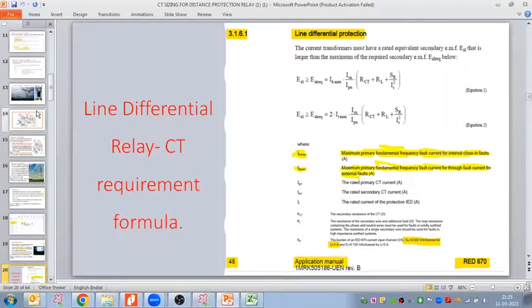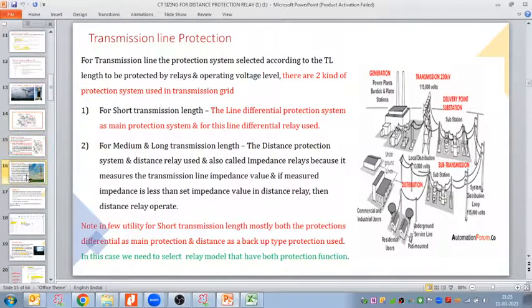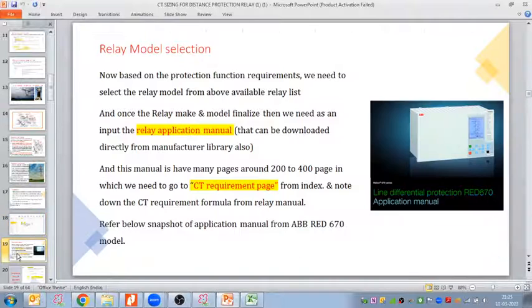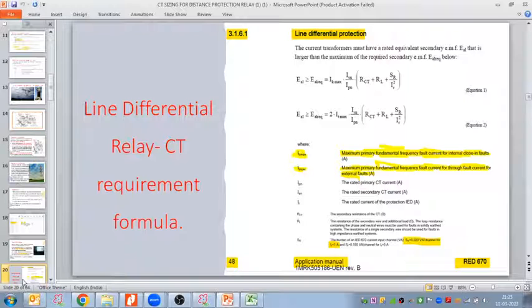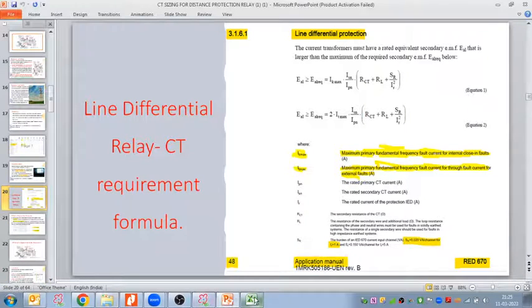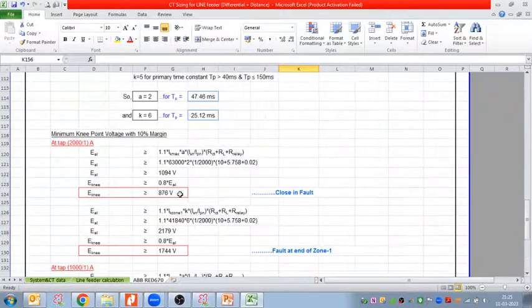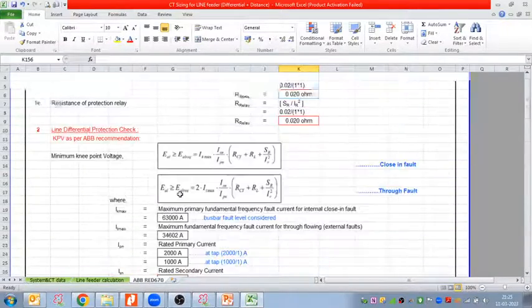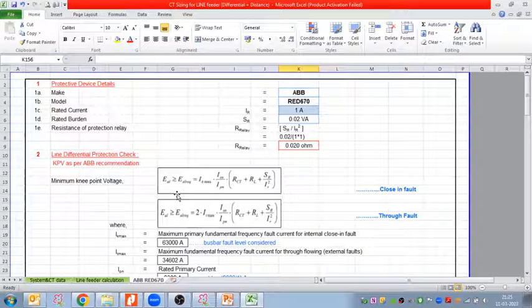Now, relay selection we have to do. In relay selection, we need to check the CT requirement. Once relay selection is done, from the relay application manual we need to take the CT requirement formula. This we have written here, and this formula ultimately we need to solve. If I open my Excel calculation sheet for the CT knee point voltage calculations, today we will discuss only this sheet, but before coming to this sheet we are discussing the background of this sheet.